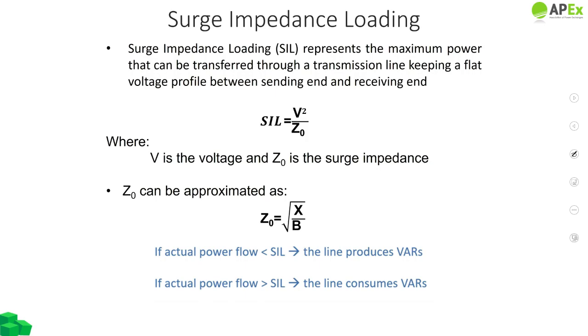The definition says surge impedance loading represents the maximum power that can be transferred through a transmission line while keeping a flat voltage profile. This means if we have a voltage at the sending end and at the receiving end, when the line is loaded at the surge impedance loading, our Vs is going to be equal to Vr — the sending end and receiving end voltage would be the same.